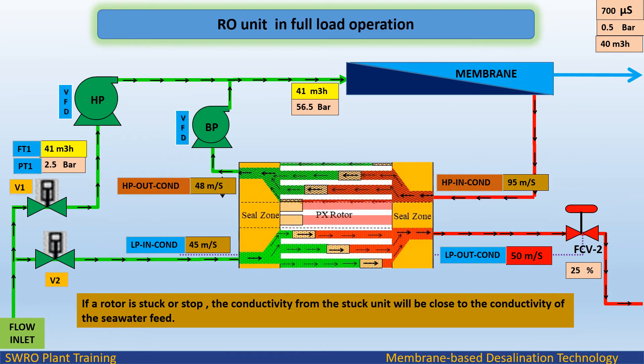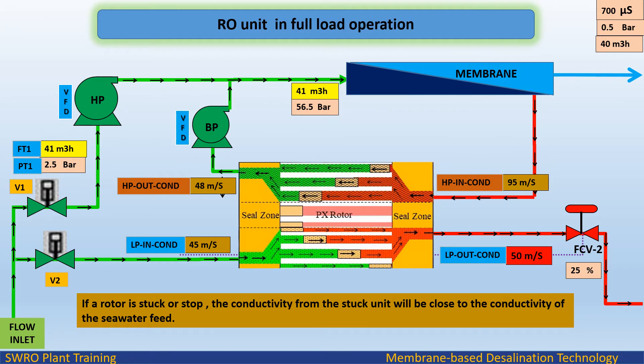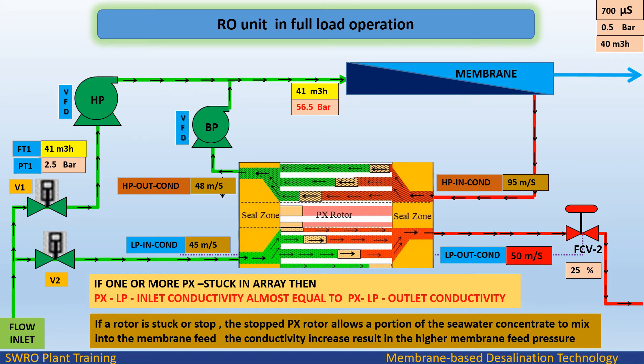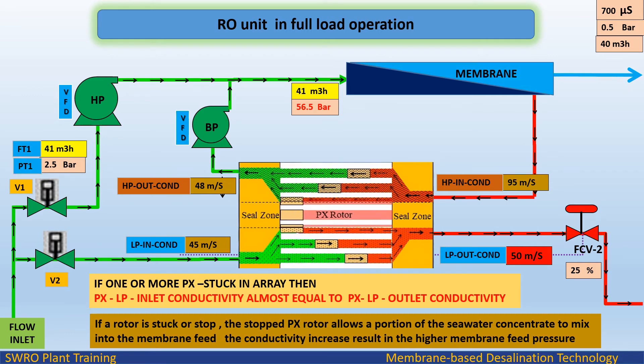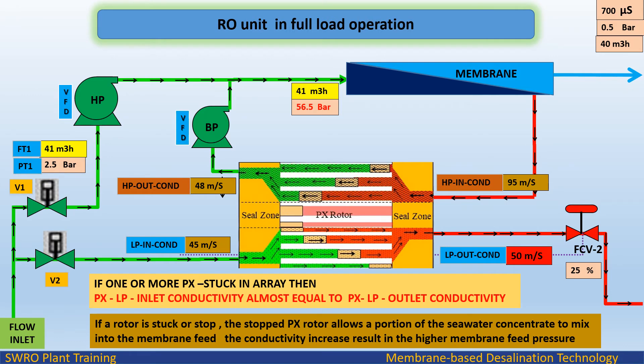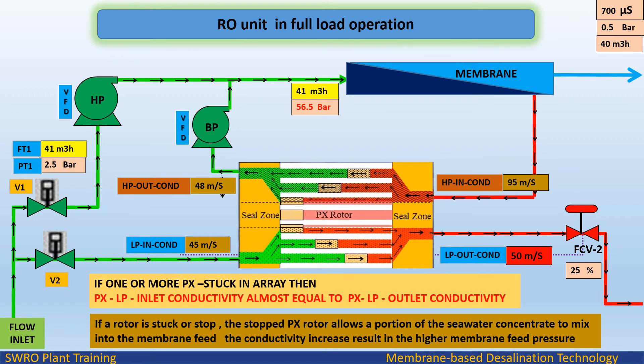If a rotor is stuck or stopped, the conductivity from the stuck unit will be close to the conductivity of the seawater feed. If one or more PX are stuck in the array, PXLP Inlet Conductivity will be almost equal to PXLP Outlet Conductivity. The stopped PX rotor allows a portion of the seawater concentrate to mix into the membrane feed, causing a conductivity increase that results in higher membrane feed pressure.